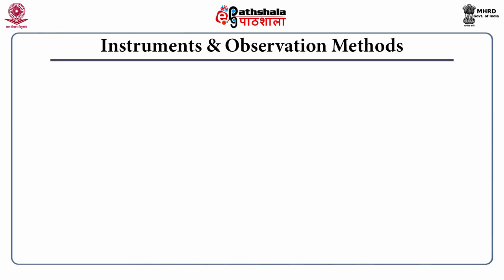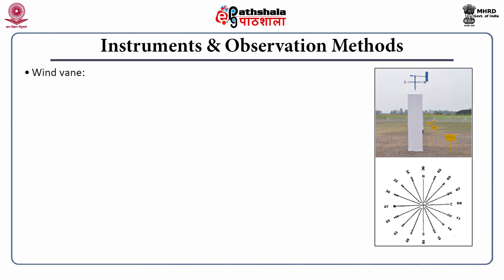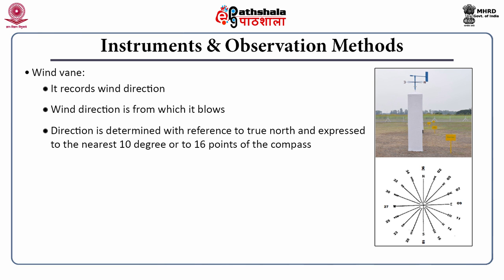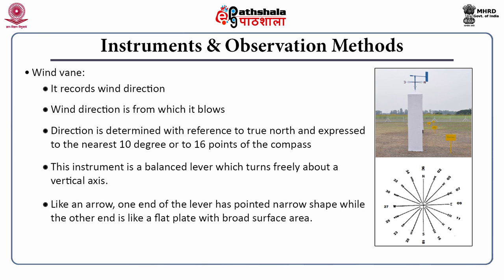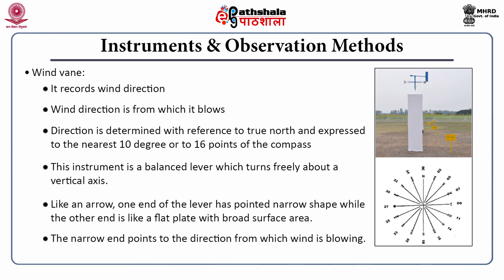Let us start with the wind vane. The wind vane records wind direction. Wind direction is the direction from which the wind blows. It is determined with reference to true north and expressed to the nearest 10 degrees or 16 points of the compass. This instrument is a balanced device which turns freely about a vertical axis. Like an arrow, one end is narrow and the other end is a flat plate, so the narrower end points to the direction from which wind is blowing.